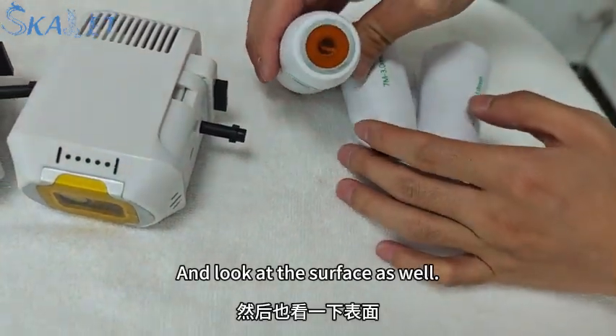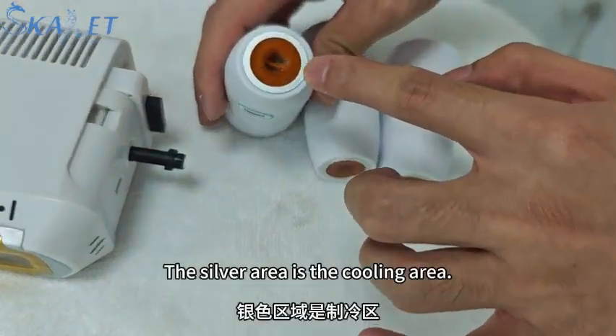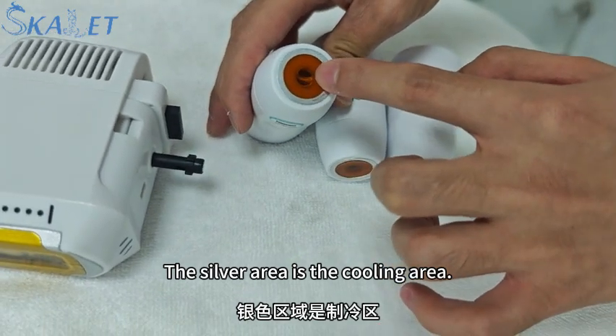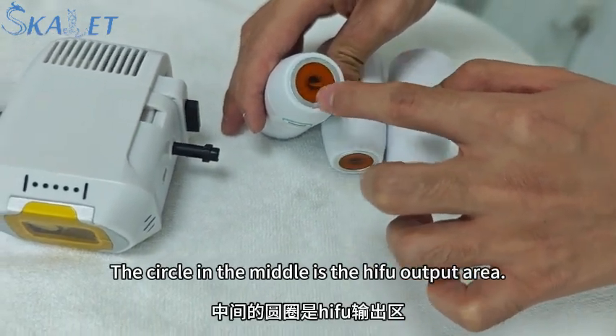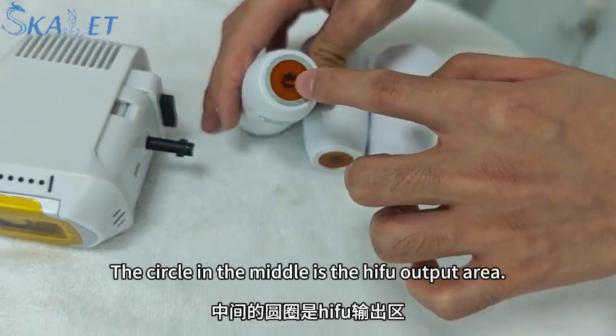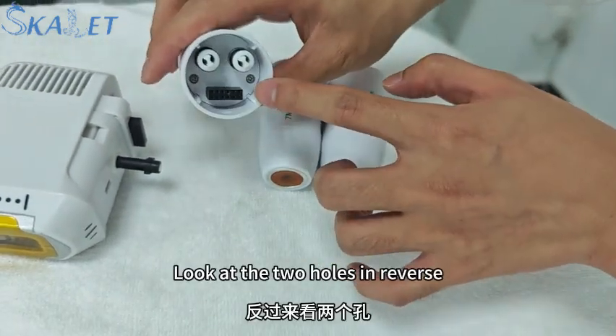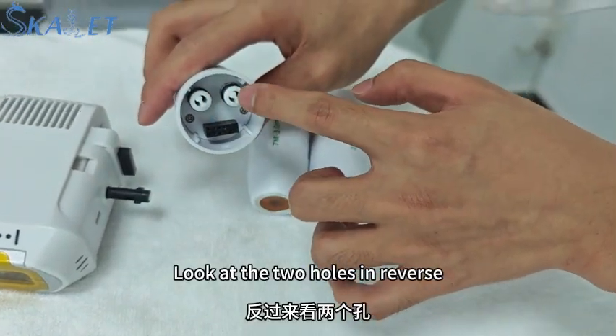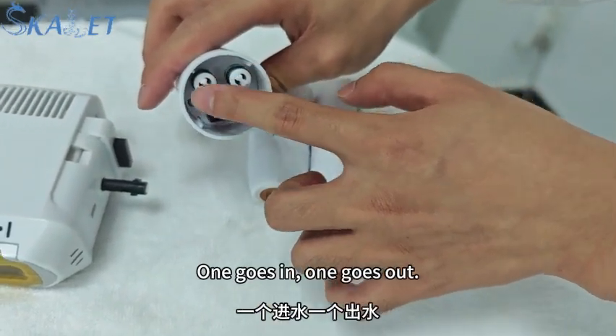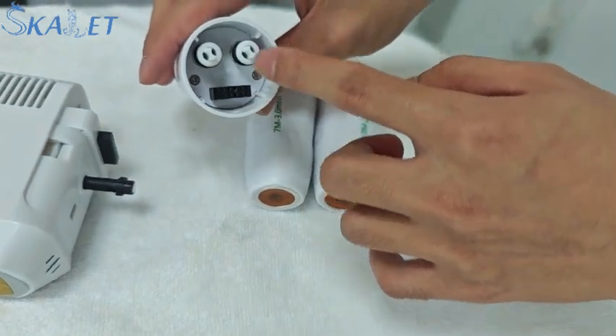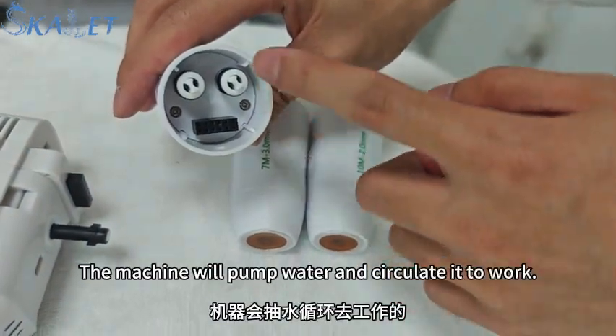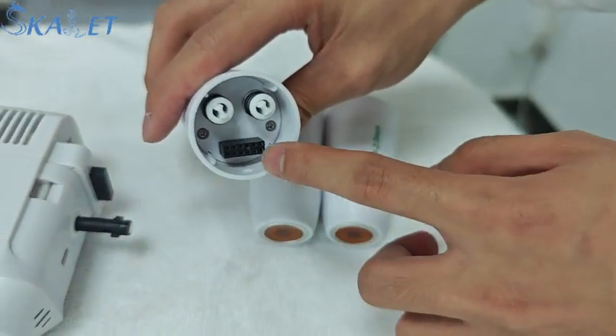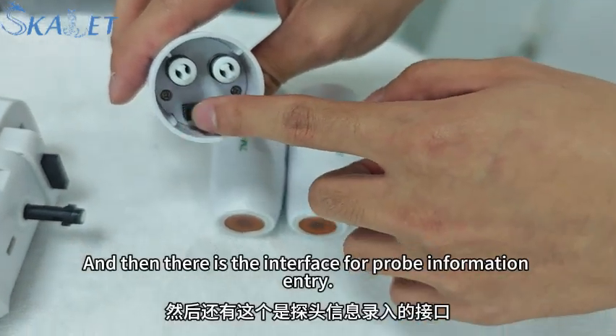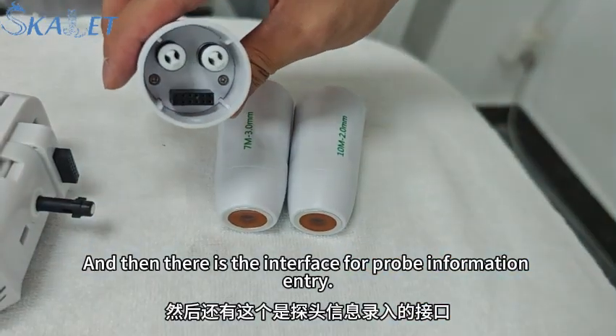And look at the surface as well. The silver area is the cooling area. The circle in the middle is the HIFU output area. Look at the 2 holes in reverse. One goes in, one goes out. The machine will pump water and circulate it to work. And then there is the interface for probe information entry.